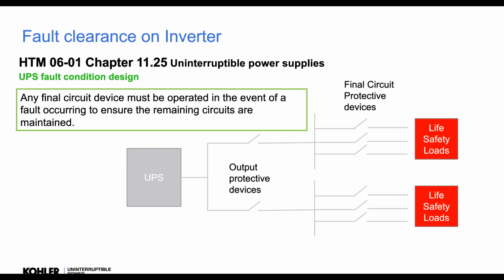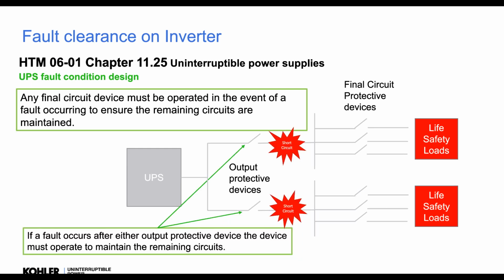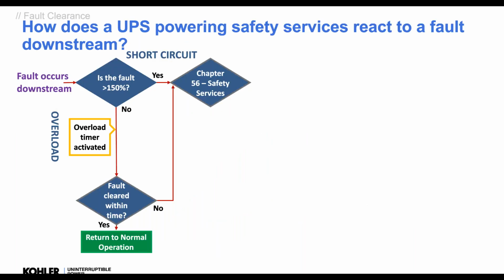Of course, if everything's life safety, we do see this a lot. We have a central UPS here, maybe a 200 kilowatt, 300 kilowatt, feeding multiple IT. We have to be able to operate these devices if there is a problem. Quite often we're seeing 50 amp devices here to feed 10 kVA UPSs, and we need to operate these if there's an issue. It's not being done properly in a lot of places, and this is one of the reasons why we run these events, because we see a lot of things aren't right.